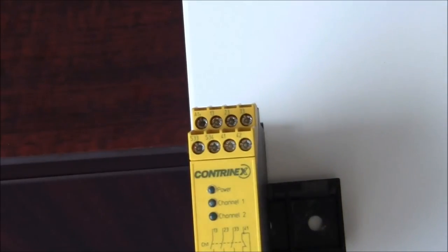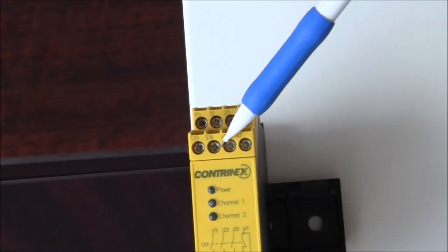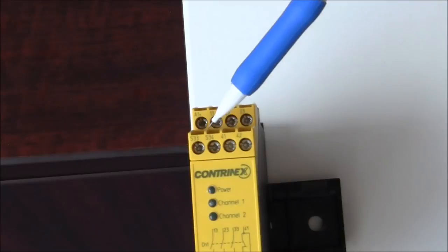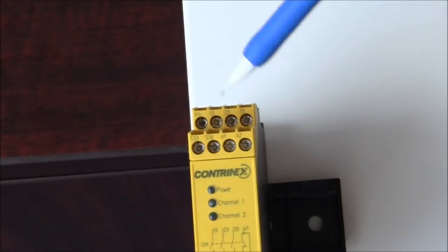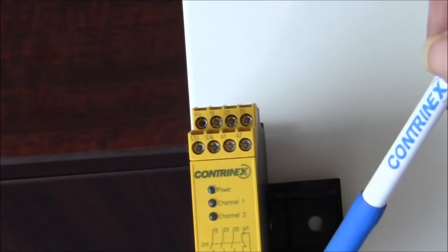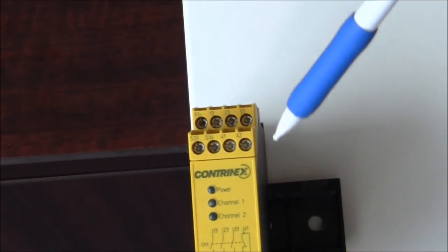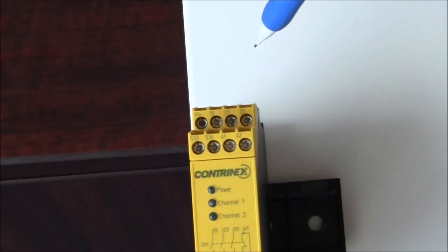This image is of the top of the relay. I want you to take note of this contact S33 and this contact S34. These are the automatic restart contacts. Right here there is a terminal 33 and on the bottom matching up there is a terminal 34. Don't get those confused while you're wiring or your light curtain will not operate.